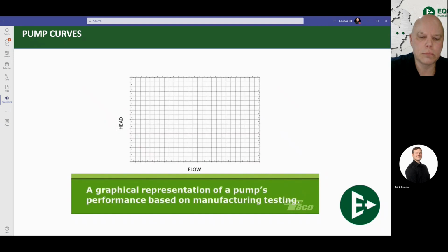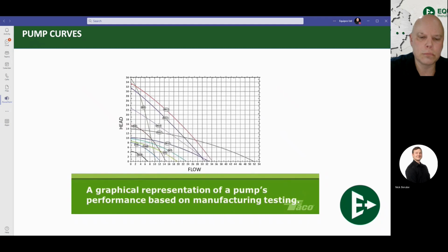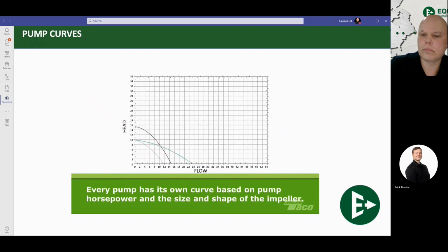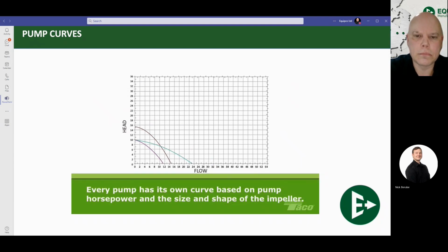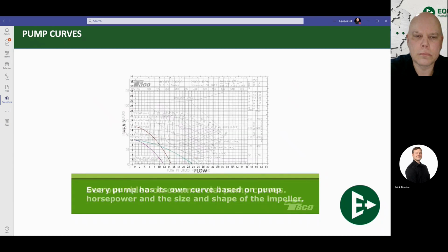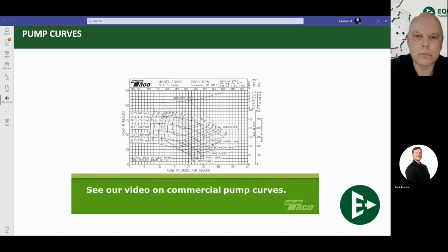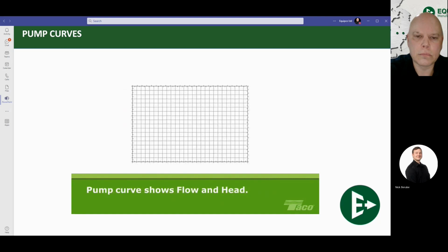A pump performance curve, usually just called a pump curve, is a graphical representation of the performance of a pump based on testing by the pump manufacturer. Every pump has its own curve, and those curves vary widely from pump to pump. The variations depend on many factors, such as the horsepower of the pump and the size and the shape of the impeller. Pump curves can be used to provide information on many other elements of pump performance. Some of these are of interest only for designing commercial systems. We'll cover these in another video lesson available on the TACO website. In the simplest and most widely used form, a pump curve shows two vital pump performance factors, flow and head.